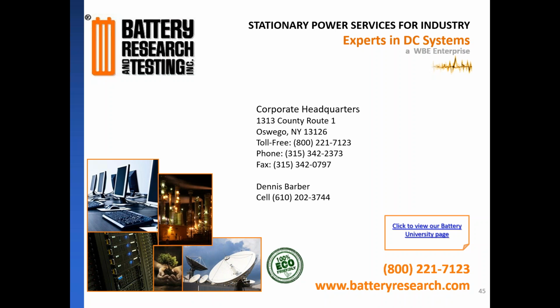Okay. Well, yeah, we were getting a low DC current alarm on a couple of these chargers. I wasn't sure if that was a major thing or not. Again, that would be usually, yeah, an LCA or a low current alarm is usually when the rectifier is at 0. LCA, and where I've come across that have usually been parallel rectifiers.